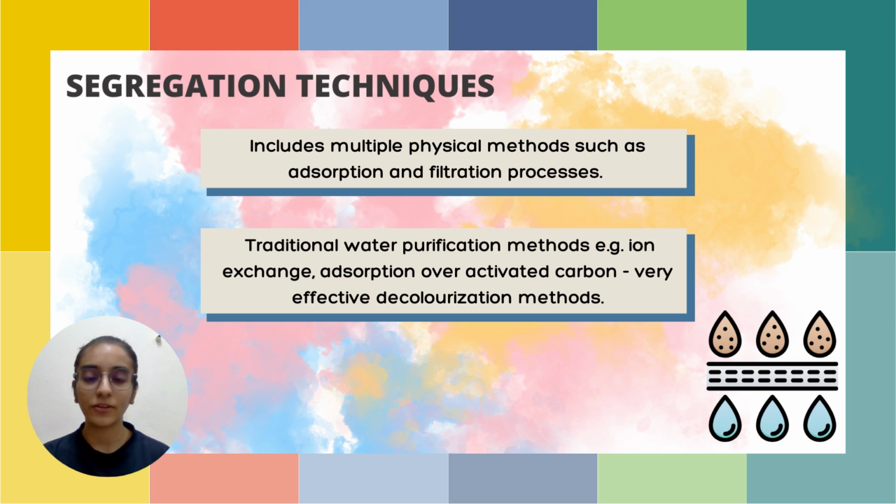Adsorption, on the other hand, is a process where a solid is used for removing a soluble substance from the water. During wastewater filtration through activated carbon, the solid is the activated carbon, and the contaminants will adhere to the surface of these carbon granules or become trapped in the small pores of the activated carbon.